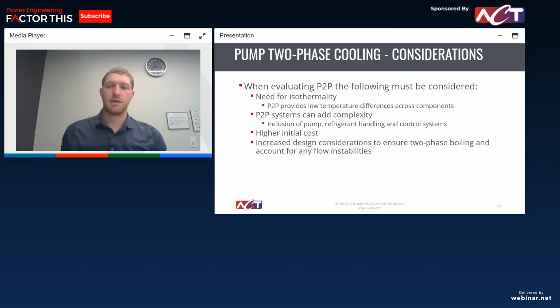So some considerations when we're talking about pump two-phase. One of the main ones we see when we have customers that are looking for a pump two-phase solution is the isothermality. It can be very important for a lot of electrical components to keep that temperature difference across components very low. So in those types of applications, pump two-phase is a great solution. Some of the potential drawbacks of pump two-phase is it does add complexity. Compared to your loop thermosyphon, you add the pump. As opposed to your single phase solutions, you have to deal with refrigerant handling. You have much higher pressure in the system than a single phase loop, so there's some additional complexity there. The upfront cost is oftentimes higher due to that complexity.